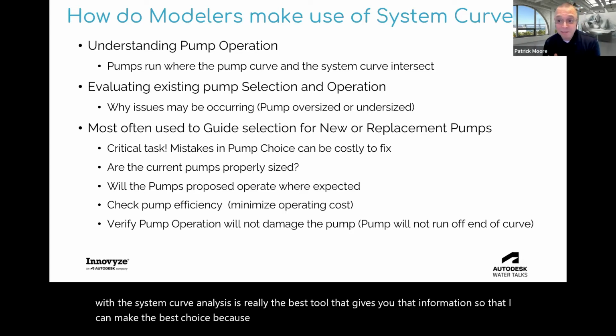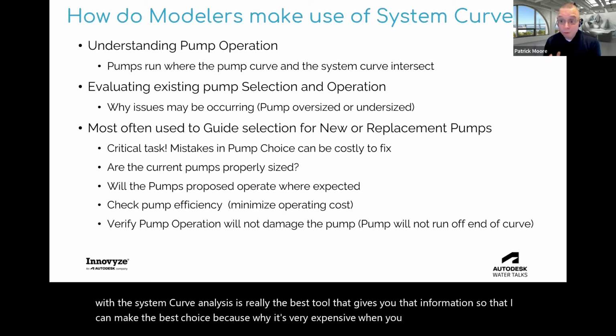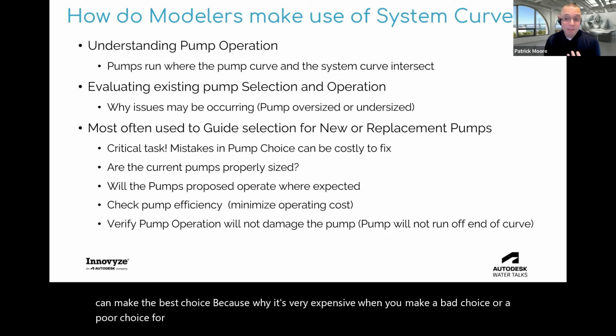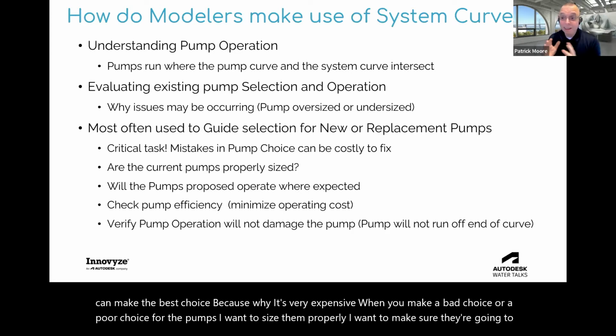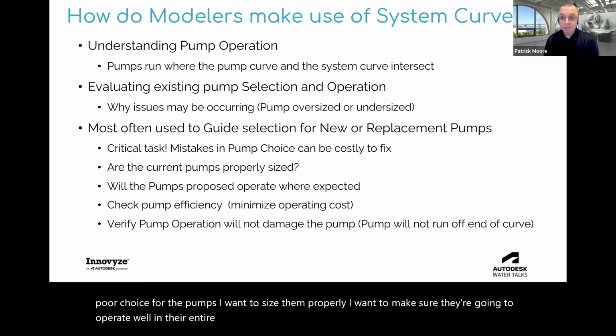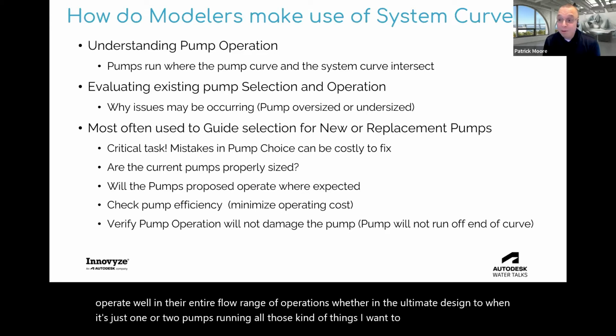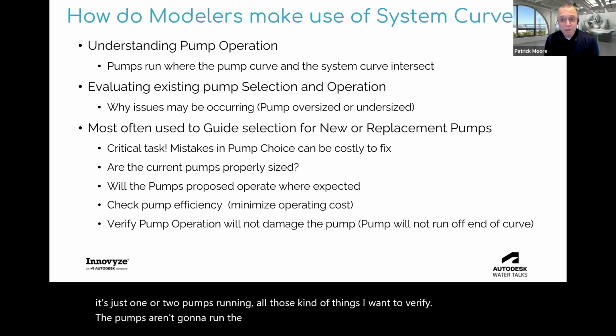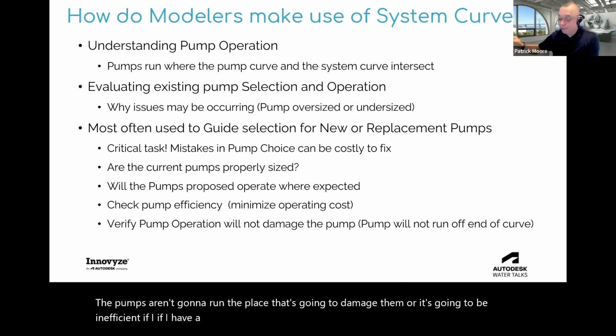Because why? It's very expensive when you make a bad choice or a poor choice for the pumps. I want to size them properly. I want to make sure they're going to operate well in their entire flow range of operations, whether in the ultimate design or when it's just one or two pumps running, all those kinds of things. I want to verify the pumps aren't going to run in a place that's going to damage them or be inefficient. If I have a system curve, that's really going to help me do those things and do it well.